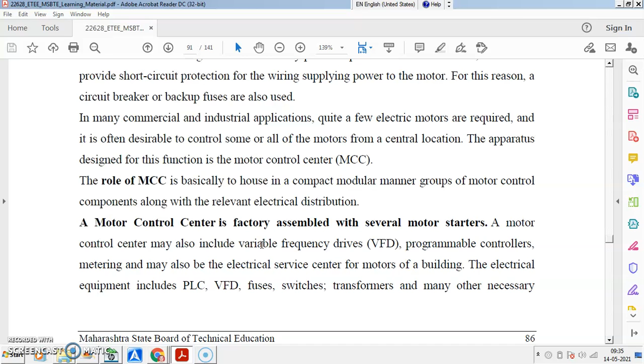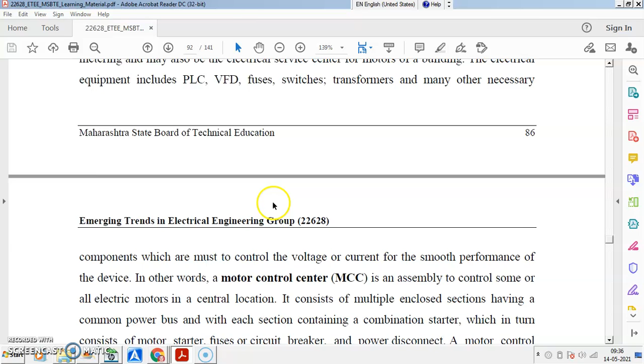The electrical equipment like PLC, VFD, fuses, switches, transformers, and many other necessary components are a must to control the voltage and current of the motor for smooth performance. In this case, the motor control center or MCC is an assembly to control one or more electric motors in a central location. It consists of multiple enclosed sections having a common power bus, with each section containing a combination of starter, which in turn consists of motor starter, fuses, circuit breaker, power disconnect.